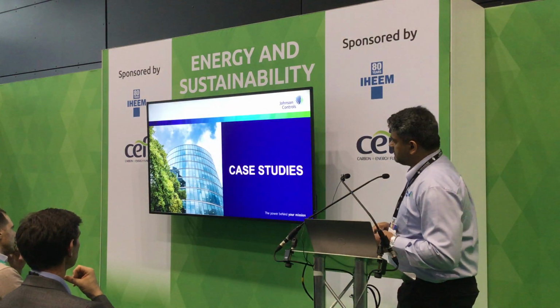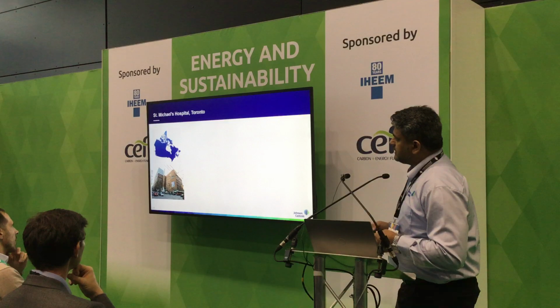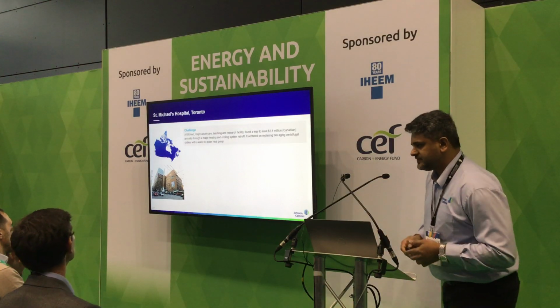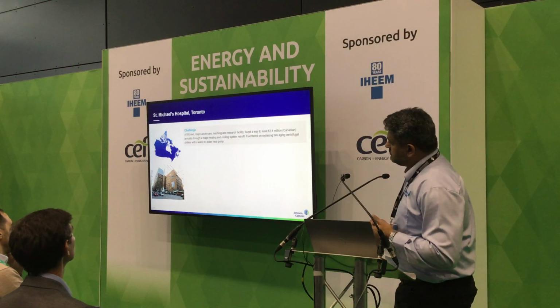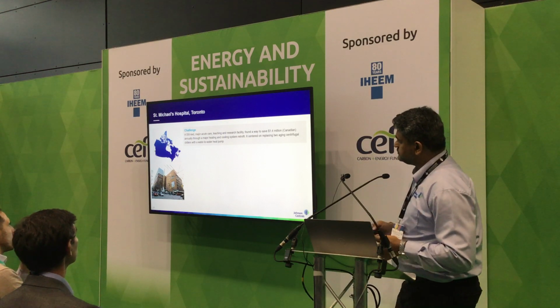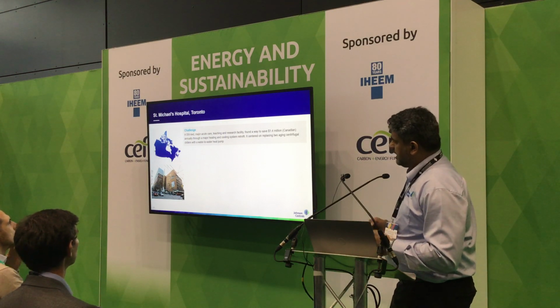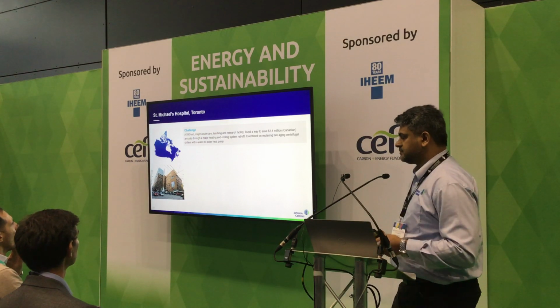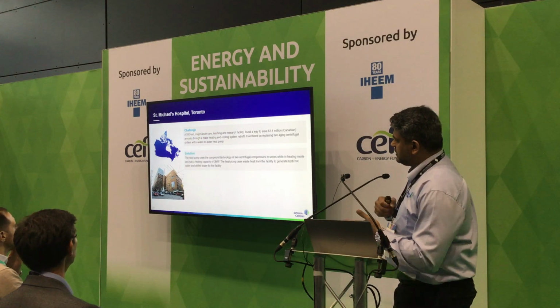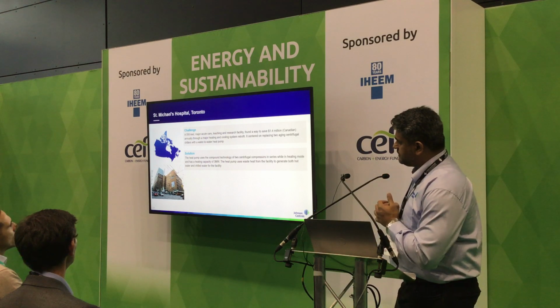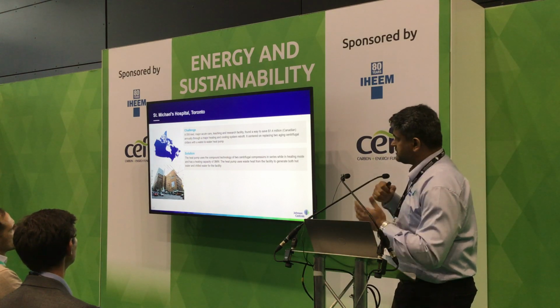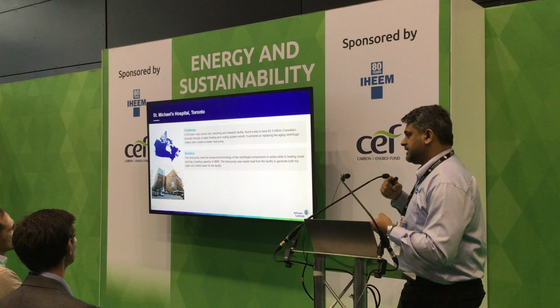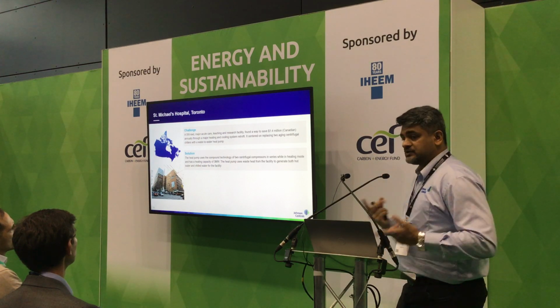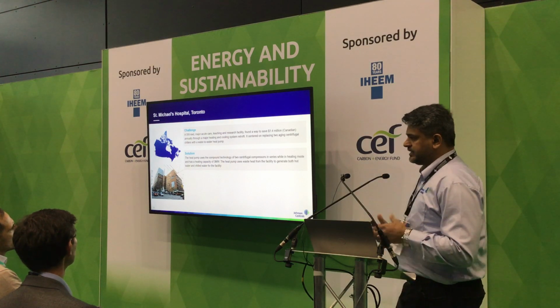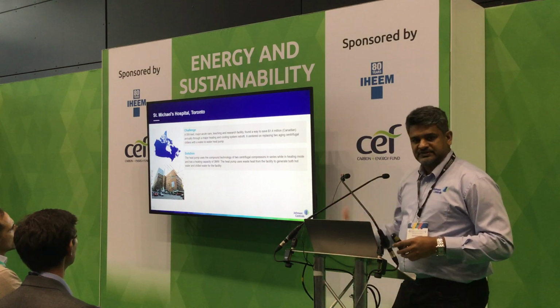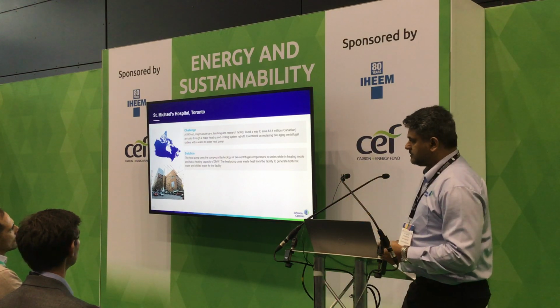A few case studies that we've done. St. Michael's Hospital in Toronto, a fairly large facility, quite old. They managed to save around 1.4 million annually by retrofitting their existing system. What we did was employ a technology using 2 centrifugal compressors, which in heating mode can give you 3 megawatts of heating, and also during that time it uses waste heat from the facility, and it also delivers your cooling.